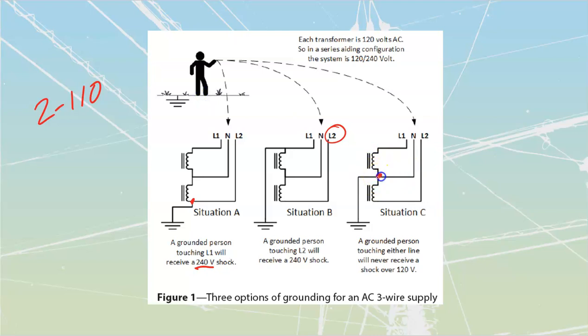Our safest situation is to ground the neutral point of the transformer. When that is done, they would have no more than 120 to this one and 120 to this one. Yet we would still be able to get 240 across from line to line.